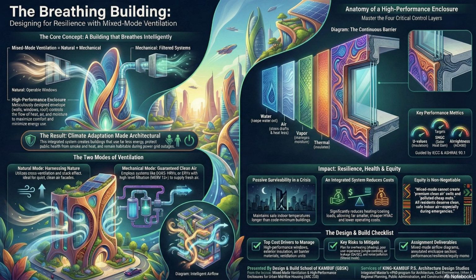It sounds like this climate analysis isn't just some preliminary step. It's a design input that has a huge impact on the budget, right? It has to. If you find out your city spends 70% of the year in the yellow and red zones, your whole budget allocation has to shift dramatically. Precisely. If your building is in, say, Phoenix, or in a wildfire-prone area like San Francisco, places where red zone events are frequent and predictable, investing heavily in natural ventilation features might be secondary. Your priority is elsewhere. Your primary capital spending has to be poured into that high-performance enclosure to keep the heat out and into robust, reliable, highly filtered mechanical systems.